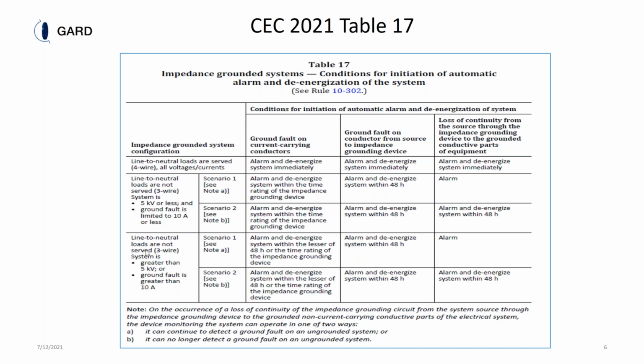Third item is a neutral grounding device greater than 5 kV or greater than 10 amps. Now you have a low resistance grounded system. So you have an integral low resistance grounded system. You must alarm and de-energize within 48 hours, depending on where the fault is, on the solidly grounded system or ungrounded system.